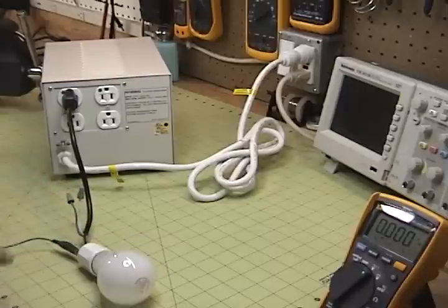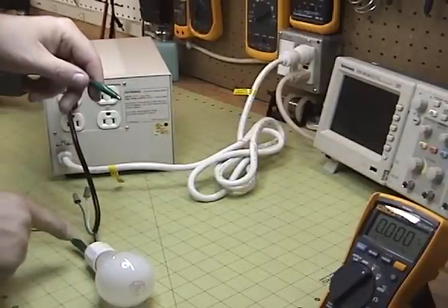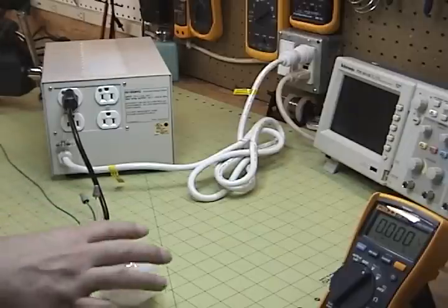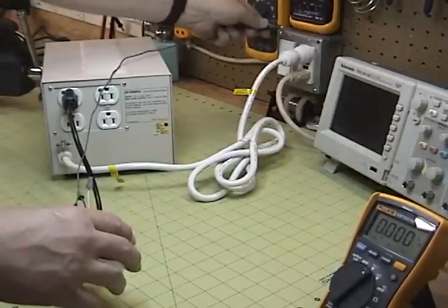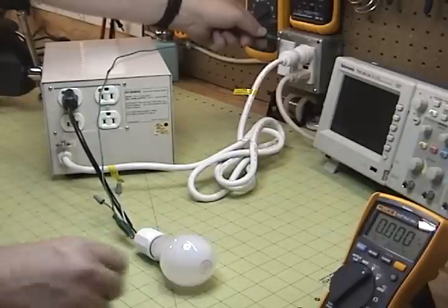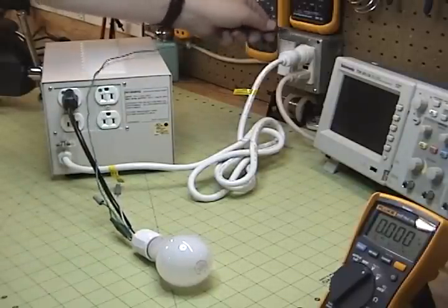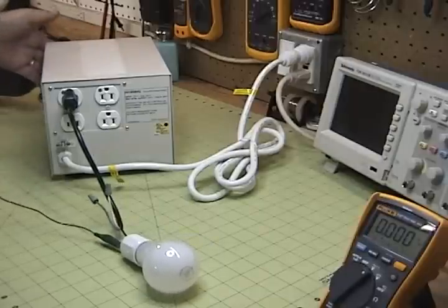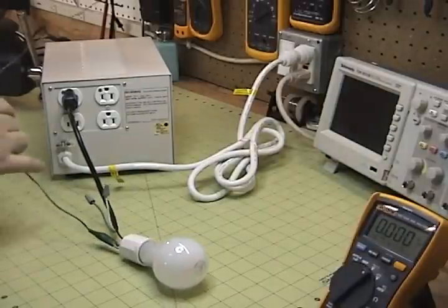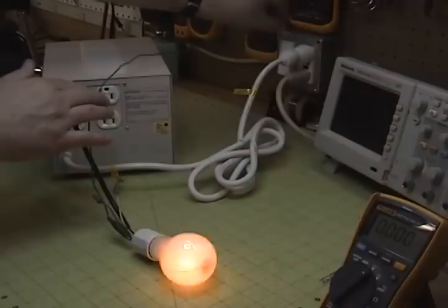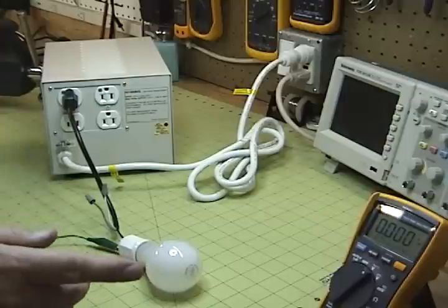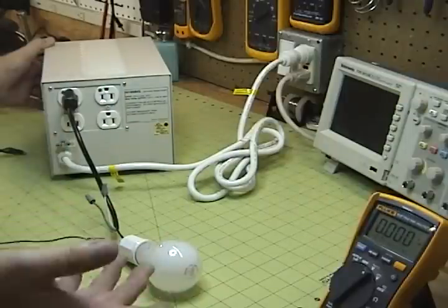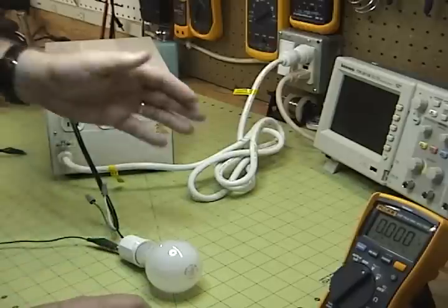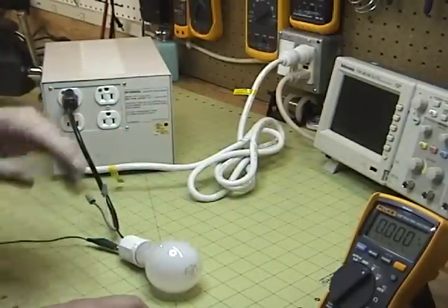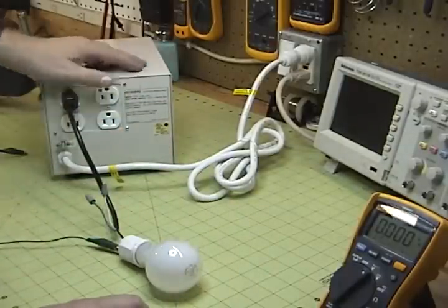I'll hook up the alligator clip to the other side, then touch it to the same grounding point over here on the case. I'll set the light bulb there and turn on the transformer, making this a hot circuit. Because that secondary is strapped to ground, the light bulb still lights. That would be really bad for you or your test gear, because if you become a fault to ground, regular earth ground, you're going to light up just like that bulb did. But we're going to show that we can fix that.